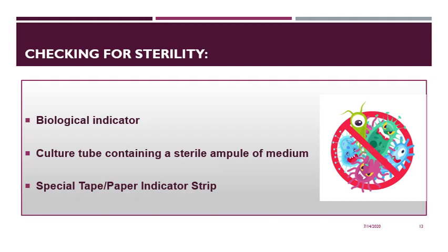This tape, which changes color upon sufficient heating, is autoclaved with a load of material. If the word appears on the tape or if the color changes after autoclaving, the material is supposed to be sterile. These approaches are convenient and save time but are not as reliable as the use of the bacterial endospores.